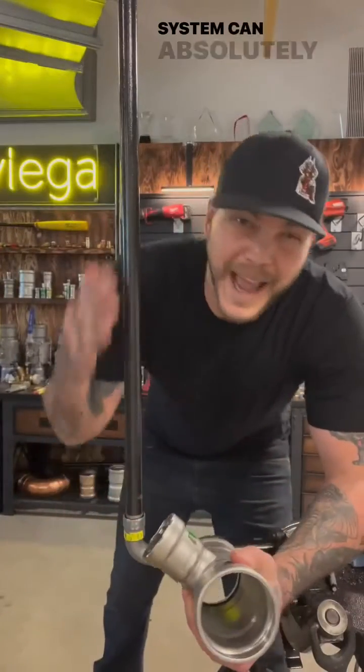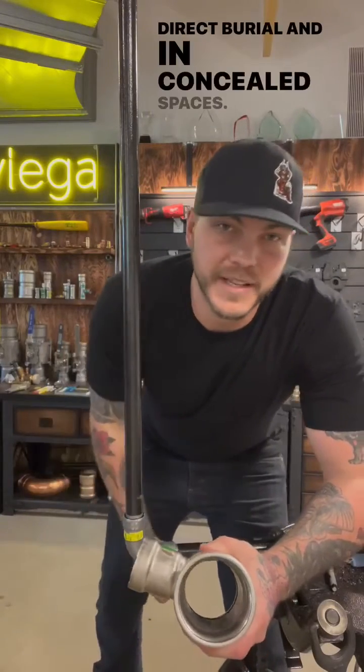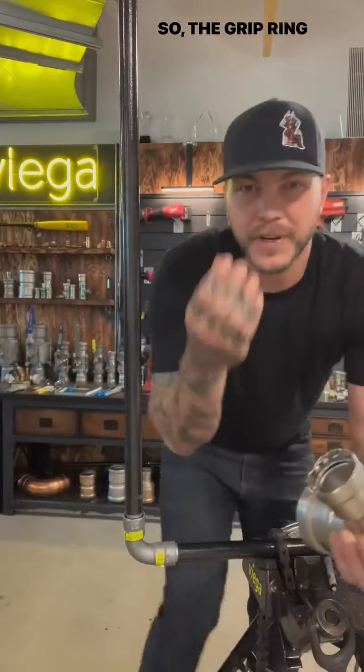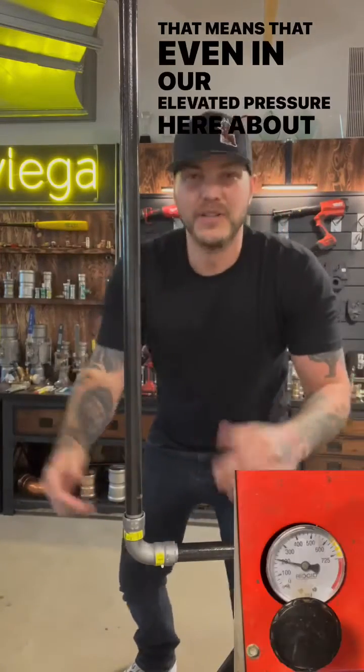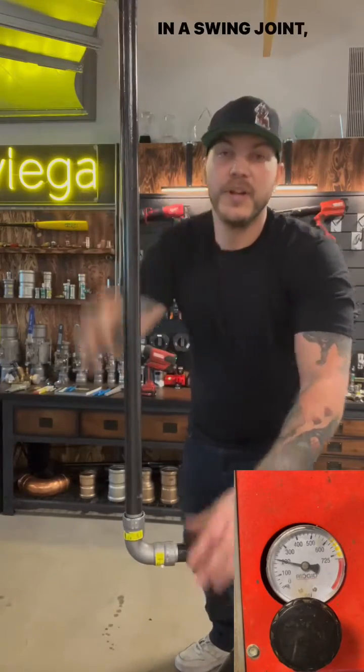Now the mega press system can absolutely be utilized as a swing joint, also for direct burial and in concealed spaces. That's because on the inside of that hub, it's nice and smooth, so the grip ring, separator ring and sealing element dig into the pipe and never move again. That means that even at our elevated pressure here, about 200 PSI, if that fitting has to twist and turn like it's going to in a swing joint, we're going to hold the pressure throughout the entire time.